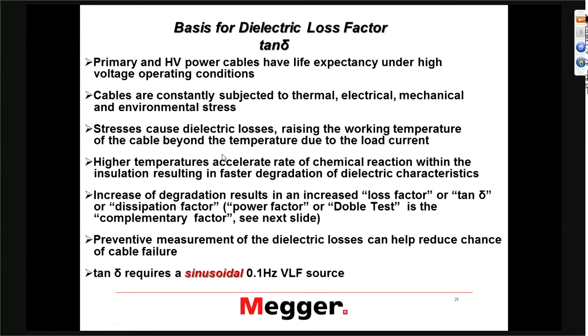Moving on to Tan Delta testing: Tan Delta is an indication of the aging condition of the cable — the increase in Tan Delta is an indication of aging, basically because you increase the dielectric losses. Tan Delta is similar to power factor testing on transformers, where we look at the power factor; here we look at the loss angle on cables. The losses are created by the deterioration of insulation, and that's what Tan Delta will tell us. It's very different when you look at frequency: if you do a 60 Hz Tan Delta test, the effect is much smaller than at 0.1 Hz. That's why it's really important to do Tan Delta testing for aging condition at 0.1 Hz, and to do this we need a sinusoidal wave shape.